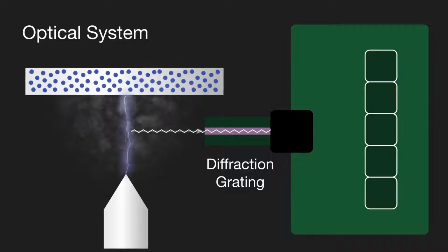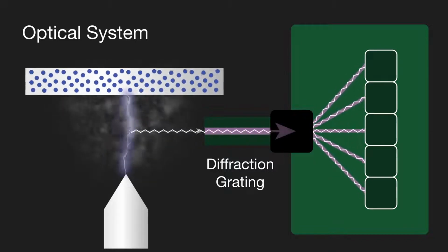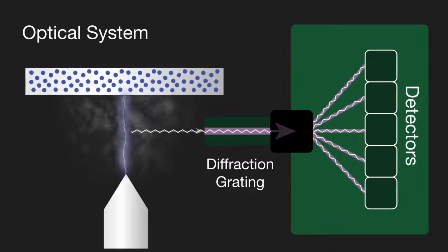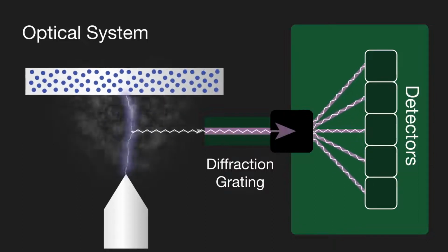The second component is an optical system. The light, the multiple optical emission lines from the vaporized sample, known as a plasma, pass into the spectrometer. A diffraction grating in the spectrometer separates the incoming light into element-specific wavelengths, and a corresponding detector measures the intensity of light for each wavelength. The intensity measured is proportional to the concentration of the element in the sample.